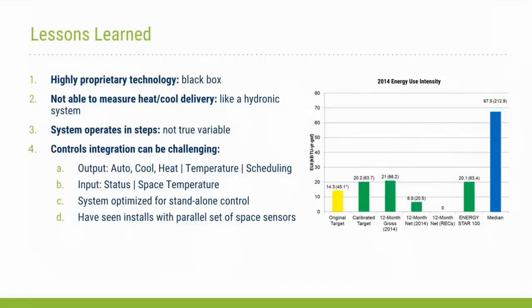The water source heat pumps we use each have 12 steps of control. As has been mentioned, controls integration can be challenging, especially if you want to do some integration with a building automation system through an open protocol. In this particular case, our biggest challenge was actually doing setpoint scheduling for each tenant agency by time of year and also linked to outdoor conditions. Eventually, we were able to integrate to the needs that we wanted, but it did take quite some time in order to particularly have setpoint limitations.